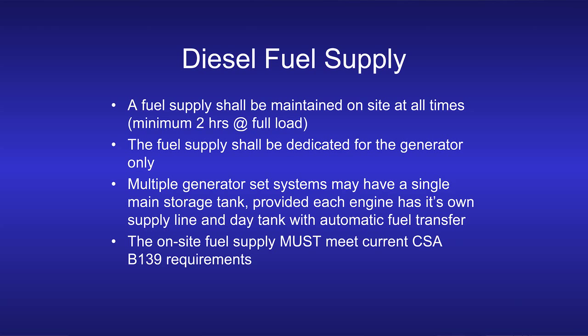But you have to have somehow a reliable fuel source, and if you're going with a liquid source like diesel, then it has to be a minimum of 2 hours supply, so that the purpose of the standard is to evacuate the building in case of an emergency. So you got 2 hours to get everybody out of the building, and that's what the generator is there for.